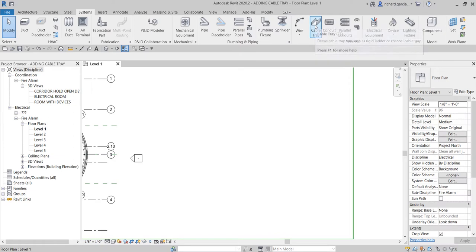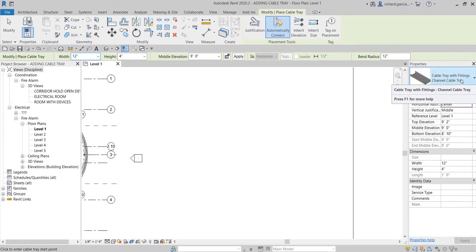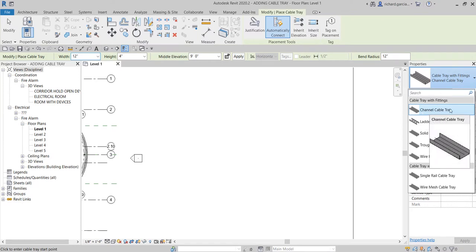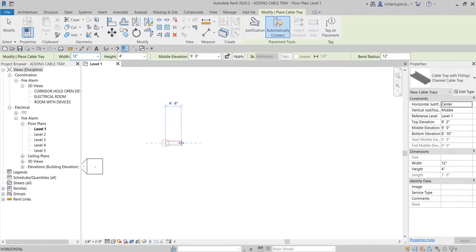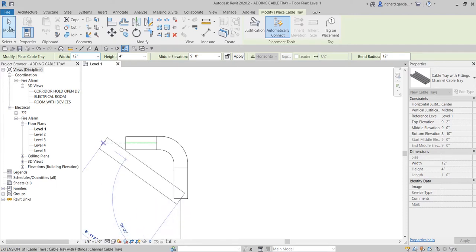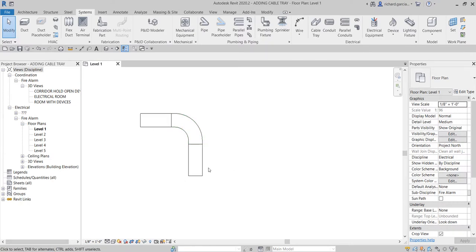Let me show you the different types of cable trays. Select Cable Tray — just like duct, you can specify the width, height, and elevation. The first type is channel cable tray, under Cable Tray with Fittings. I'll create one by picking two points. Select Modify when done. In some instances your cable tray may show as a single line — this is because of your detail level.